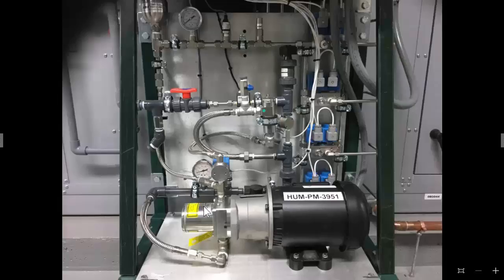Now, this pump has so much capacity to it with pushing against the nozzles that are in the ductwork itself. So if you do have a major leak that spills water, it's not a lot of water that you're losing. If you had an open line here, say this line was open, and you started the pump, water would just not come shooting out of here. It would come out with probably like a small stream that would go onto the floor. You know, it's a good amount of water, but in 5 seconds it would shut off. So the total amount of water that might spill onto the floor would be about 12 ounces maybe, not much more than that. So it's not like you're spilling a lot of water before this pressure transducer shuts the system down. So that's the big idea behind this, it shuts the system down if we have a major leak so we don't have water all over the place.